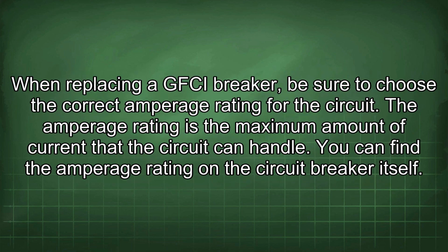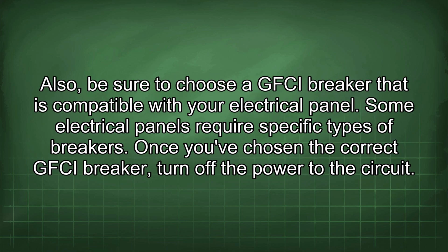When replacing a GFCI breaker, be sure to choose the correct amperage rating for the circuit. The amperage rating is the maximum amount of current that the circuit can handle. You can find the amperage rating on the circuit breaker itself. Also, be sure to choose a GFCI breaker that is compatible with your electrical panel. Some electrical panels require specific types of breakers.